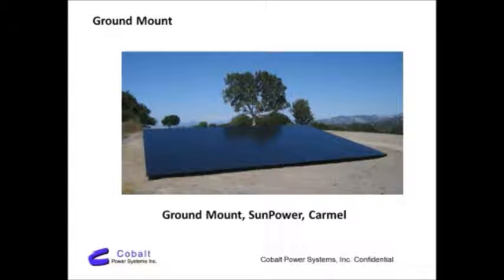And the wire is tucked up neatly underneath the solar panels. It's a special kind of wire called USE-2, which stands for Underground Service Entrance. It's the same kind of wire that PG&E buries directly in the ground with no conduit whatsoever, and it has chemicals in the insulation that animals don't like. So typically there's no problem. They're not attracted to it.